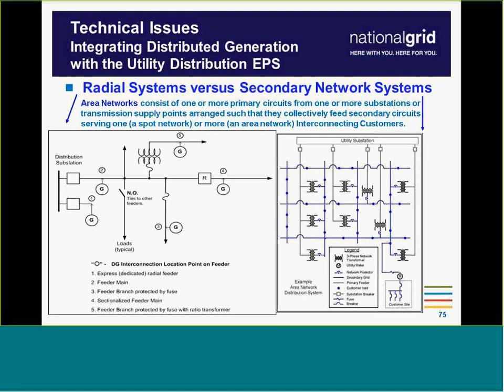If you're not sure after looking at the map, talk to CEI and make sure you're not on a network system before you interconnect. We may be able to interconnect it, but it will be a big study, and you may end up needing to run a line from somewhere outside the network. It could get complicated, so don't plan for a small project on a network to go in simply. It takes more thought because of how that system was designed, for higher reliability. There's a reason for it; it just wasn't designed with distributed generation in mind.